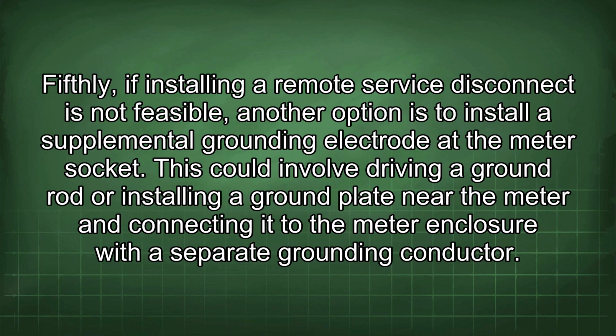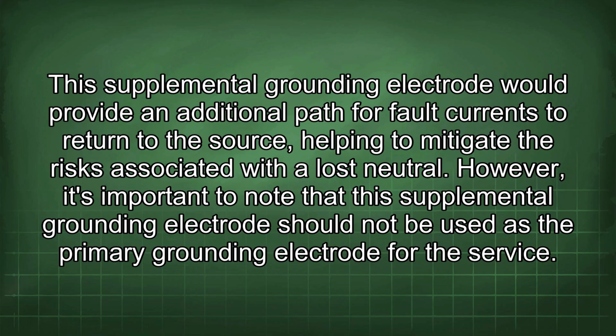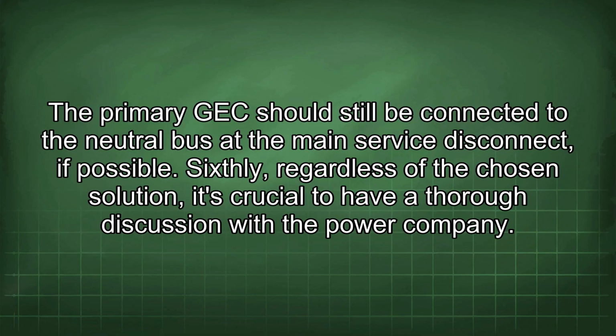This could involve driving a ground rod or installing a ground plate near the meter and connecting it to the meter enclosure with a separate grounding conductor. This supplemental grounding electrode would provide an additional path for fault currents to return to the source, helping to mitigate the risks associated with a lost neutral. However, it's important to note that this supplemental grounding electrode should not be used as the primary grounding electrode for the service. The primary GEC should still be connected to the neutral bus at the main service disconnect if possible.